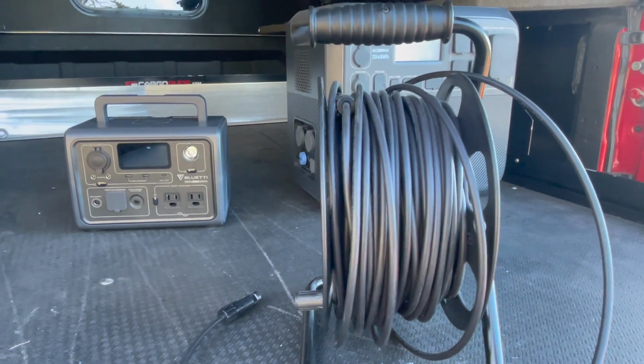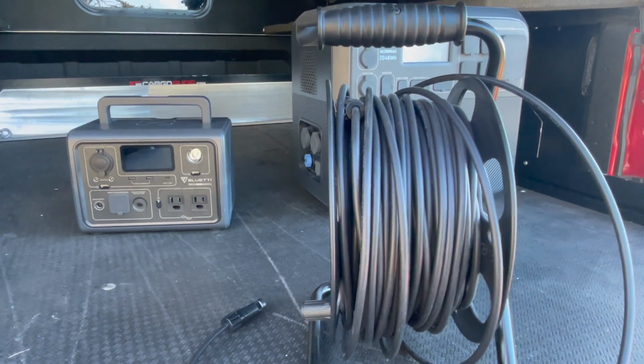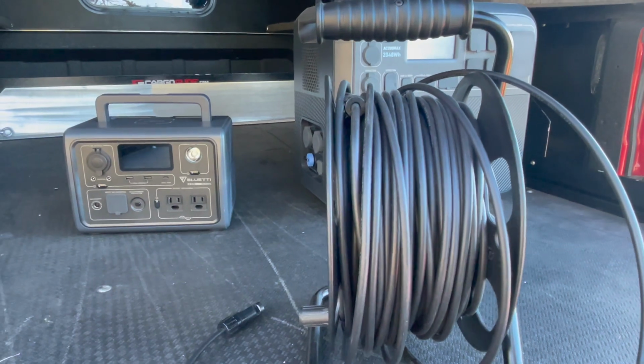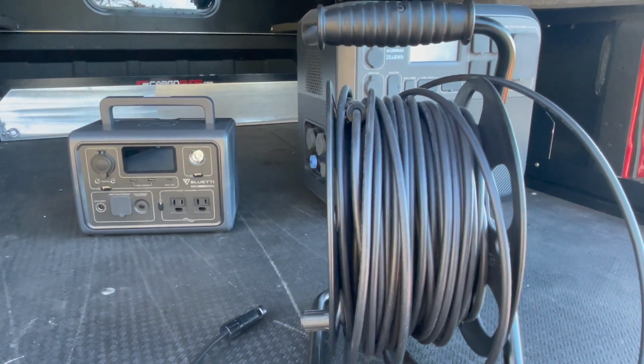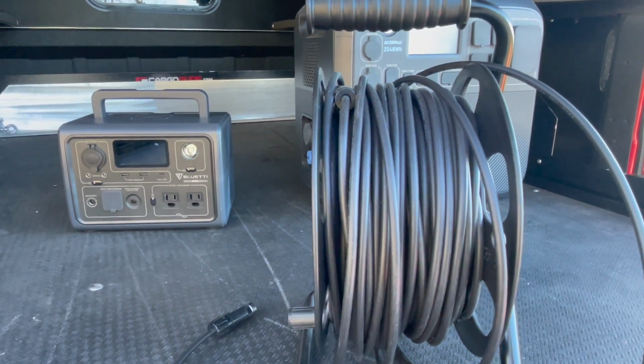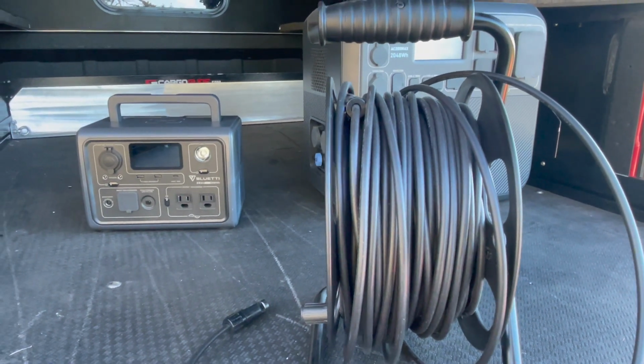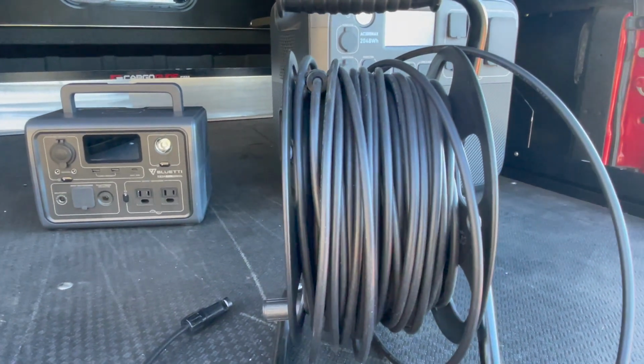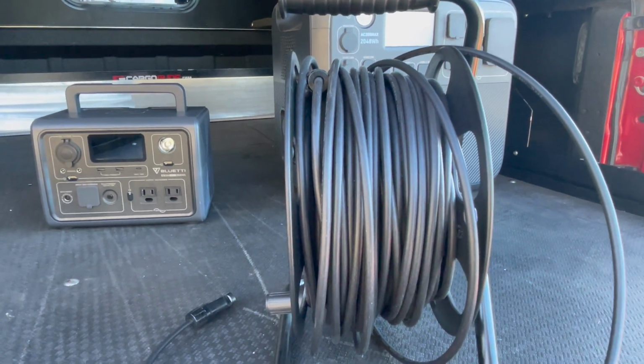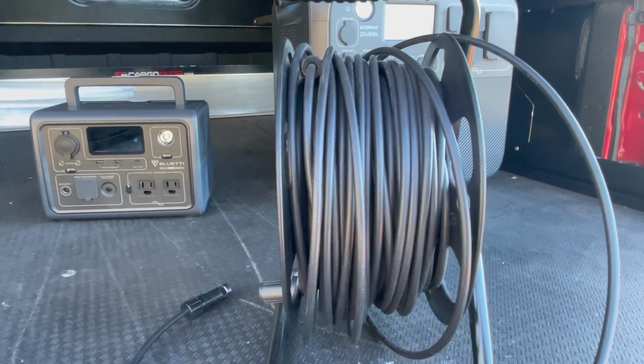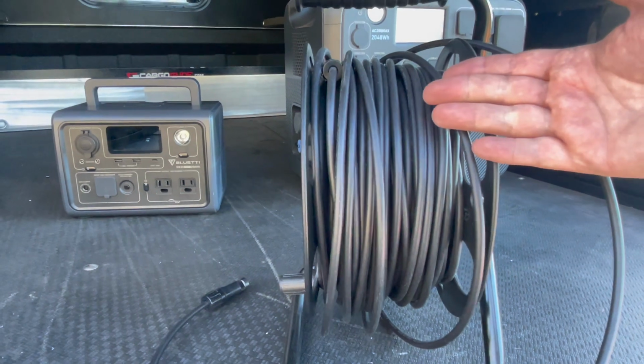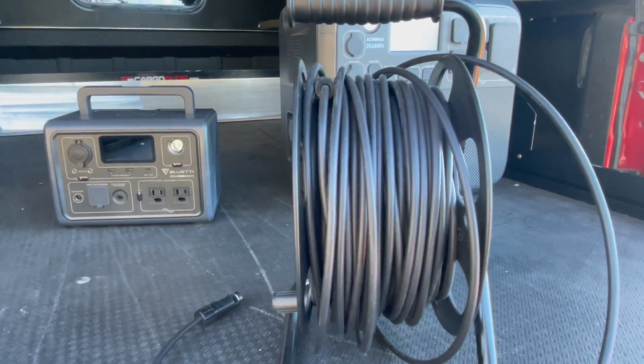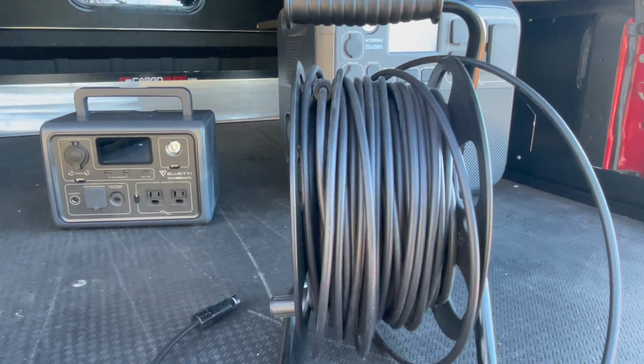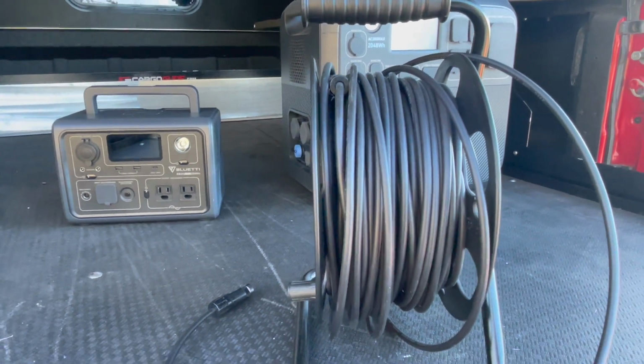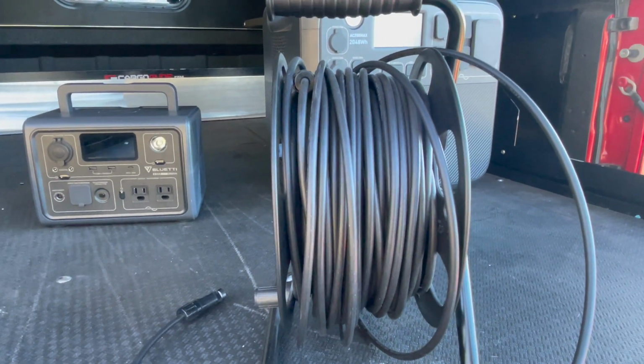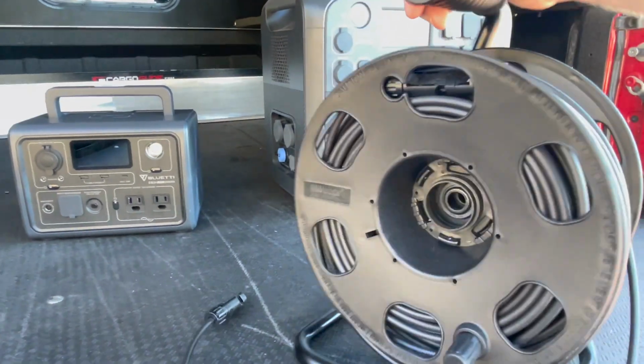Why 12 gauge? All cables lose power — there's no such thing as a cable that doesn't lose power. The amount you lose depends on the voltage, the length of the cable, and the diameter of the cable. If you make the cable 12 gauge or larger, you'll lose less than 5% of your solar energy over a 100-foot run. I only have a 50-foot run here, so I'm losing less than about 4% of my power through the cable itself. That's a good thing. With 16 gauge wire, you'd be losing more like 20%-ish of your power over the wire itself.